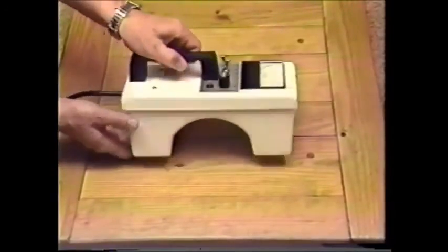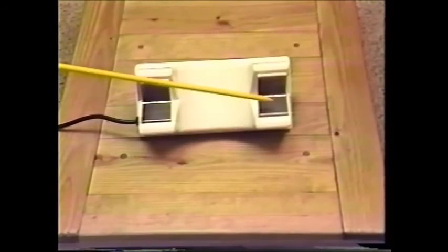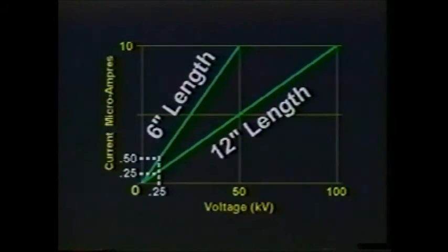The 6799 uses both a reduced voltage and length. The length between the electrodes is 6 inches and will detect a smaller defect than the 12 inch spacing. The applied voltage is 2500 volts. The scaling factors for the tester are as follows. For the dry test, the readings are referenced to the full scale values for 100 kV per foot. The 6799 uses a voltage 40 times less than the full scale test. This means the actual leakage current the tester sees must be amplified by 40 to correct for this voltage difference between the 6799 and the full scale value. The distance between the electrodes is one half that of the full scale test. This means that the actual leakage current measured by the 6799 must be divided by 2 to correct for the length between the 6799 and the full scale values. After both values are amplified, the actual amplification factor is 40 divided by 2 or a multiplication factor of 20.